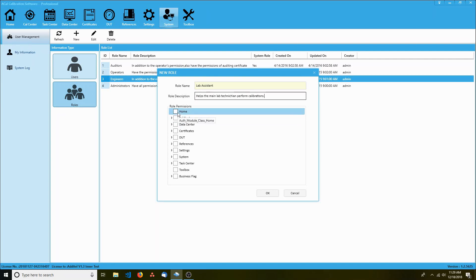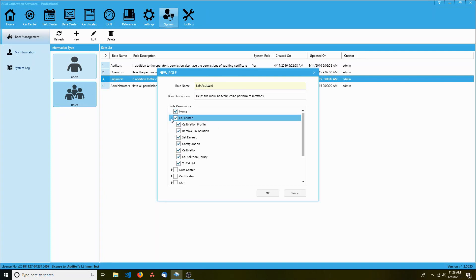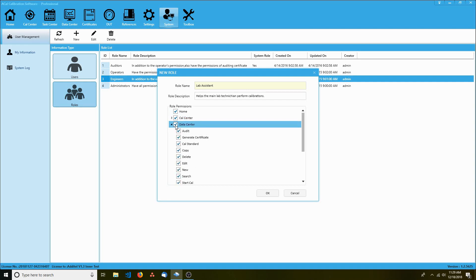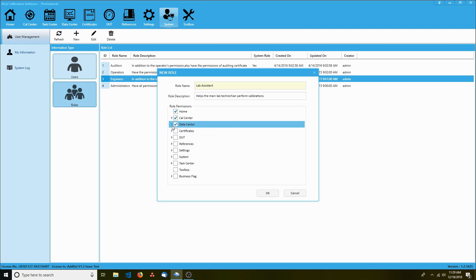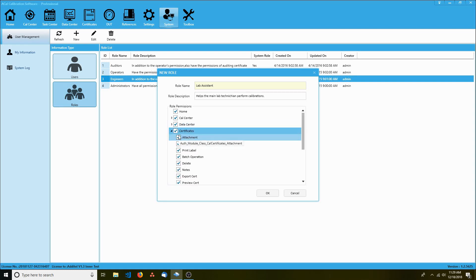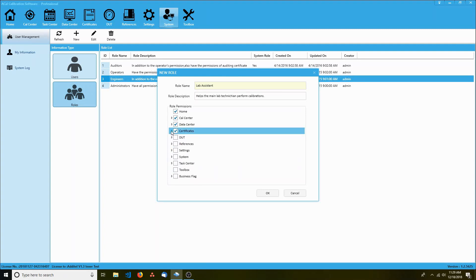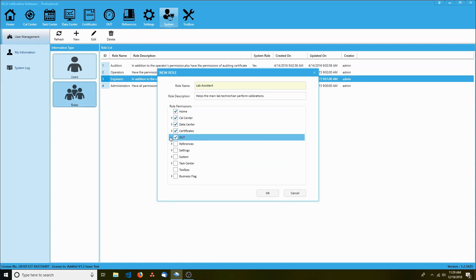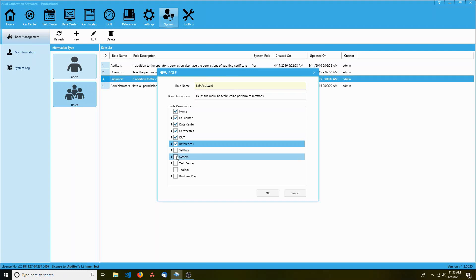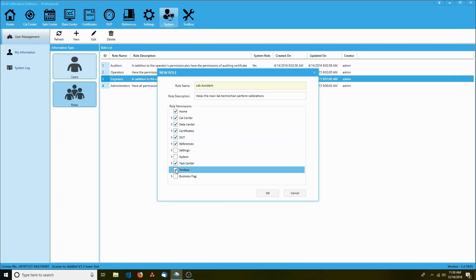Looking at the permissions, Home tab access is a good idea. As is the Cal center. Under data center, we don't really want him to be able to generate a certificate. That needs to be done by our senior lab managers. So let's give him access, but uncheck that specific option. He needs to see certs, but shouldn't be able to delete them. He does need access to DUTs and references. But we don't want him worrying about settings or system properties. The rest of the options are alright though. Now that we're done, click OK.